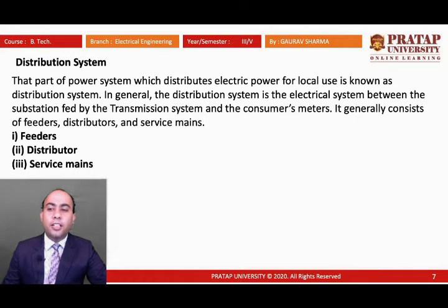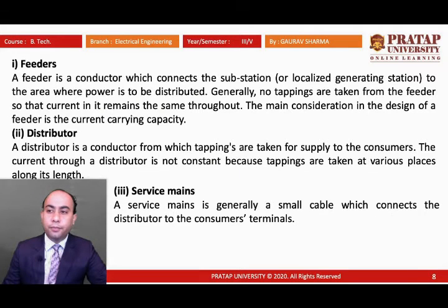These three categories are the feeders, distributors, and the service mains. Now, a feeder is a conductor which connects the substation to the area where power is distributed. Generally, no tappings are taken from the feeder, so the current in it remains the same throughout. The main consideration in the design of a feeder is the current carrying capacity.